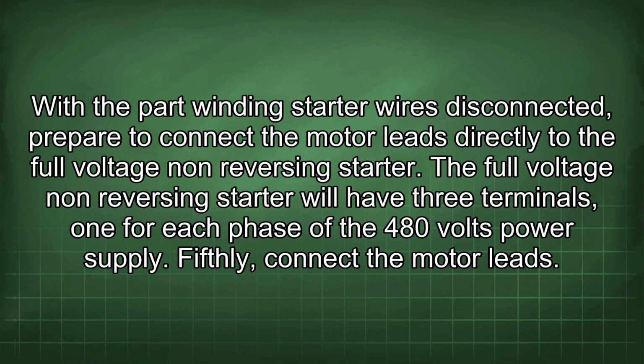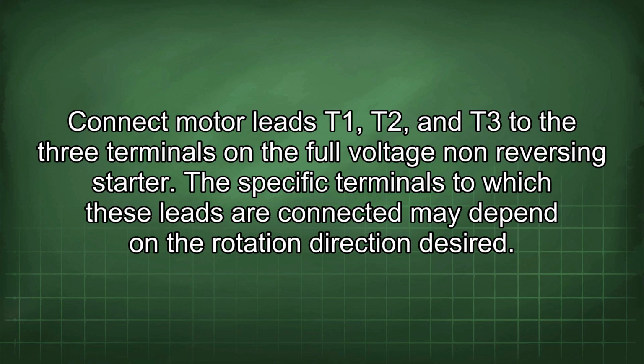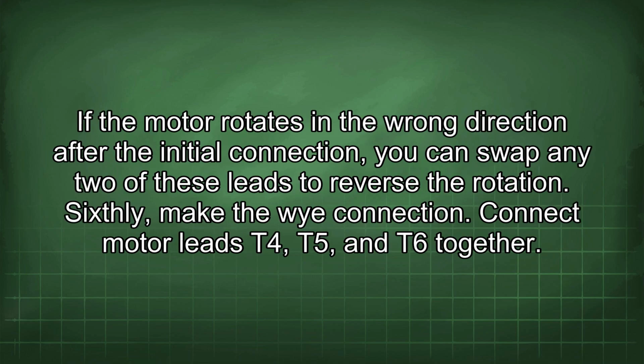Fifthly, connect the motor leads. Connect motor leads T1, T2, and T3 to the 3 terminals in the full voltage non-reversing starter. The specific terminals to which these leads are connected may depend on the rotation direction desired. If the motor rotates in the wrong direction after the initial connection, you can swap any 2 of these leads to reverse the rotation. Sixthly, make the Y connection.